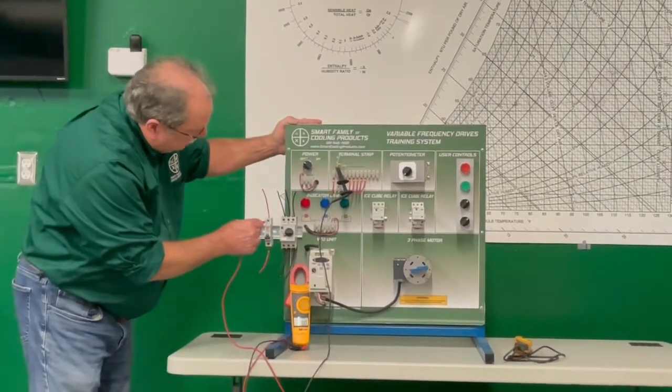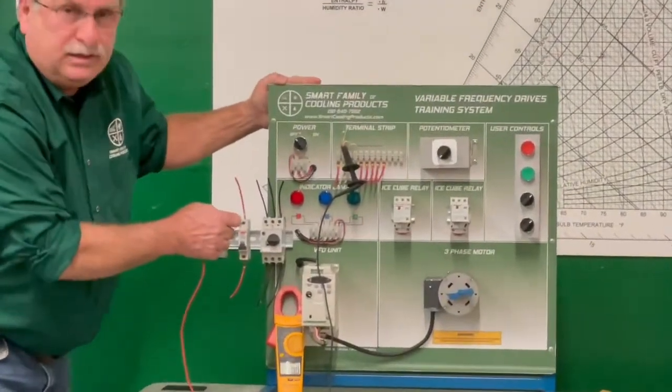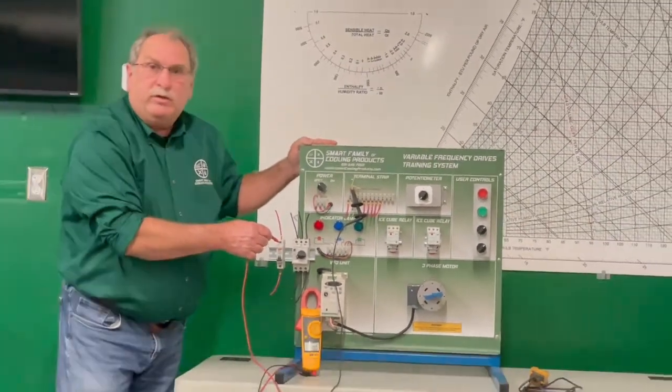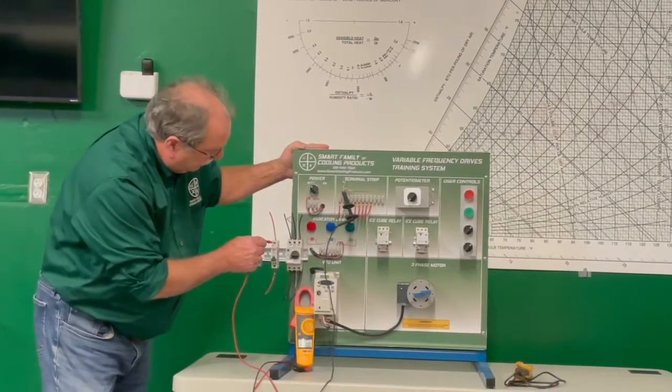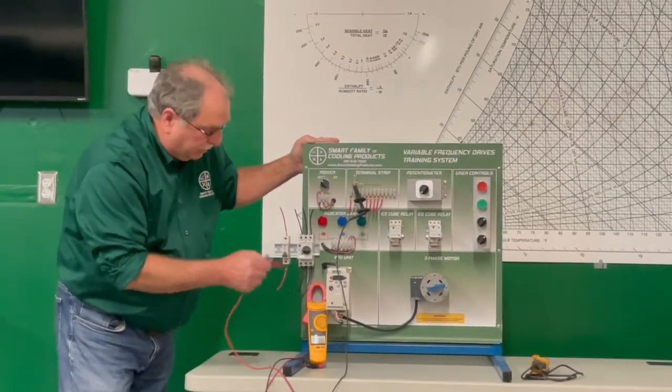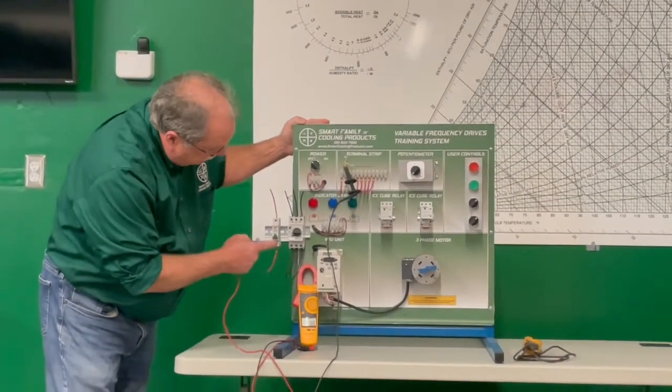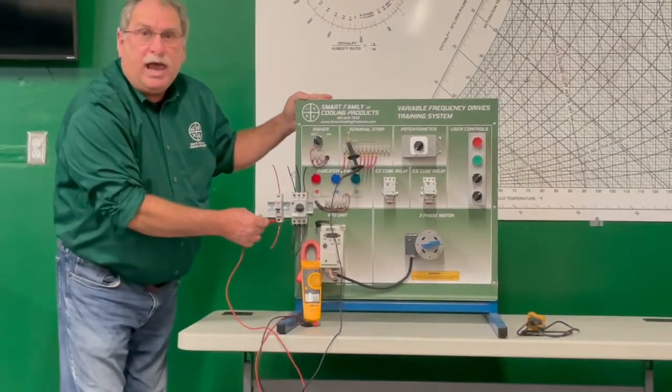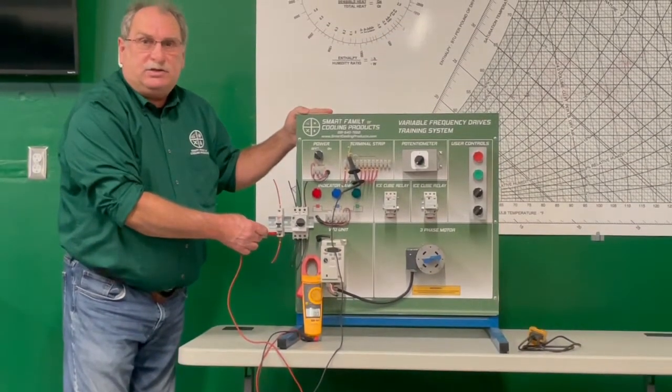And so this would be the first thing in the electrical circuit to look at. So if I check the top of it, I'd expect that I got power coming from the transformer or the power source going to my meter. So I would expect it at the top of the single-pole breaker and I'll look for it. And then if the breaker's turned on, I would expect it out of there. That's always the place to start when you're testing.